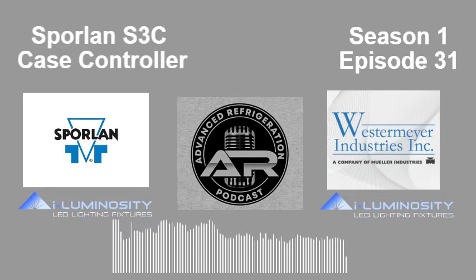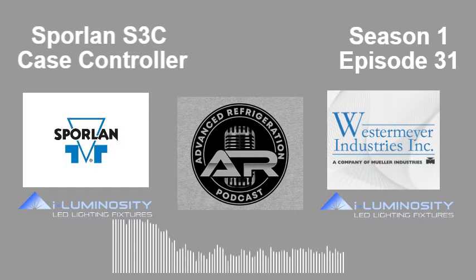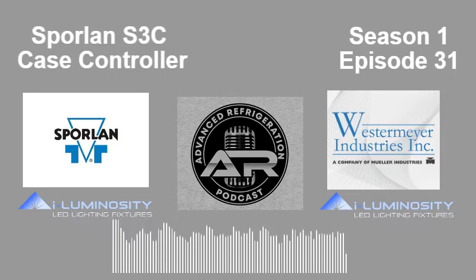Refrigerant in the system can cause us all kinds of grief. 100 years ago, when you only had R12, R22 and 502, it was simple. Now we've got a new refrigerant seemingly every week. If we don't have that programmed correctly, we've got to go in and change it. And the poor guy out on the job site doesn't always have the ability to change every single thing. There's a limit to what they can do.